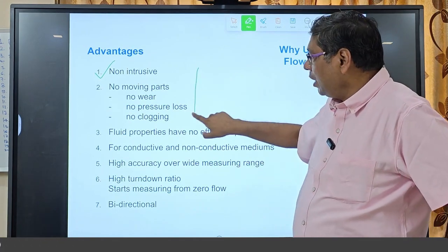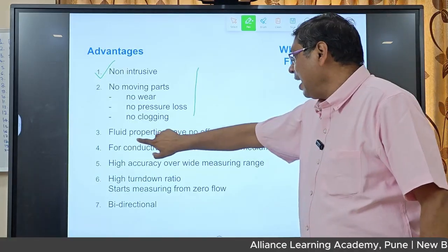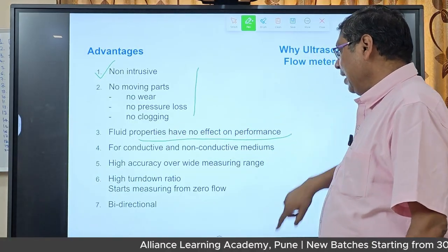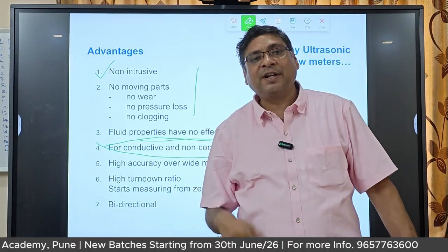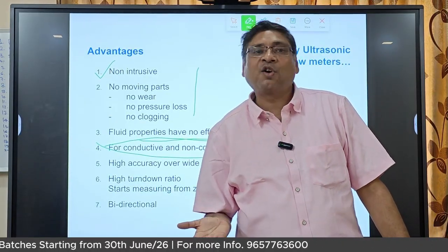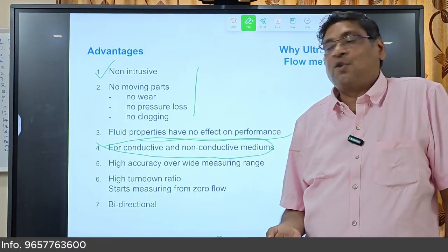Then non-moving parts, as we saw in the construction. Fluid properties have no effect on performance. Conductive and non-conductive, both kinds of media we can measure with ultrasound. In electromagnetic, we cannot use non-conductive. That is applicable only for conductive fluids.